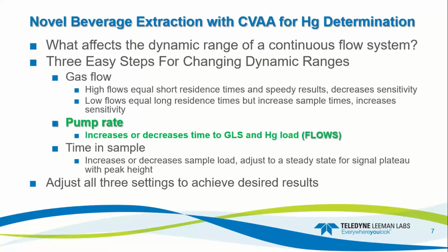Well, typically, there's 3 easy steps for changing a dynamic range. High gas flows are going to equal short residence times. That's going to give you speedy results, but it's also going to decrease the sensitivity. Low flows are going to give you long residence times. It's going to increase the sample time, but it increases the sensitivity.